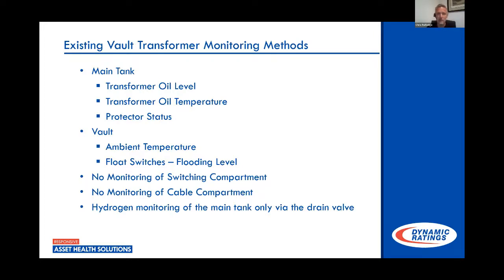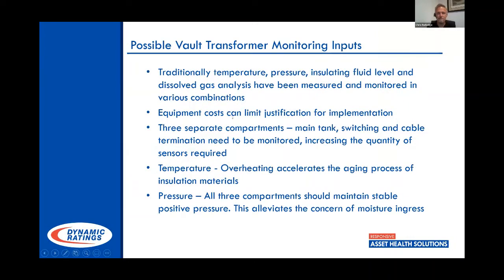The minimal that you can do is get a sample of either gas or oil from inside that transformer to really have any idea if you have a problem starting to occur, because you're not going to see it in the load and changes in load, changes in temperature. Those kind of things really aren't going to tip you off to the early stages of these problems starting to happen. So traditionally, temperature, pressure, insulating fluid level, and some people do dissolved gas on these. They'll pull their DGA samples occasionally. Of course, that's not normally a priority, and it'll get done when it gets done on whatever cyclic maintenance they're doing.